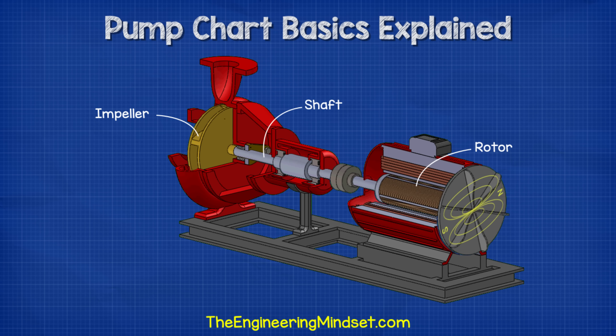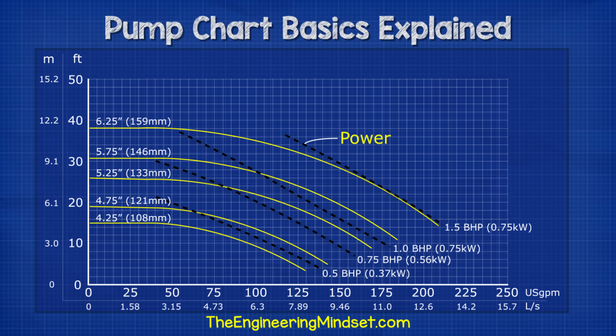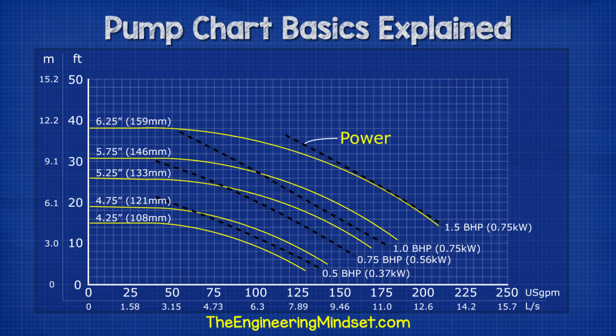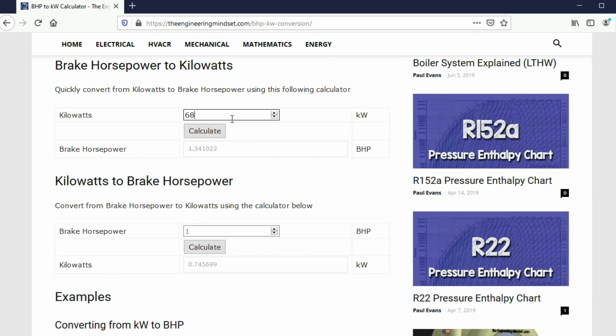Pump power. Pumps require mechanical power to spin the shaft, rotor and ultimately move the water. Pump manufacturers will usually provide a chart which plots the power requirement. In imperial units, we use brake horsepower and in the metric system, we use kilowatts. With this chart, we see the brake horsepower plotted at various intervals — as the flow rate increases, so does the power requirement. We use this chart to size our motor. For example, if we needed 125 gallons per minute with 18 feet of head, then this is between the 0.75 and the 1 horsepower lines. As this point is above the 0.75 line, this means we can't use a motor of this rating. Therefore, we will have to use a 1 brake horsepower motor, and we see the performance curve falls completely under this line. So if our head pressure calculation is wrong, then we do have some safety margin. If you want to convert between brake horsepower and kilowatts, then check out our free calculator, links down below.